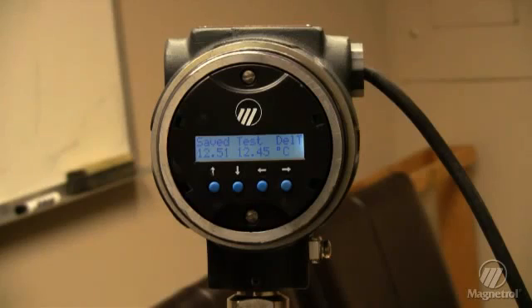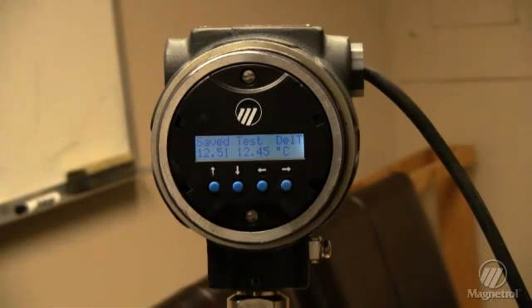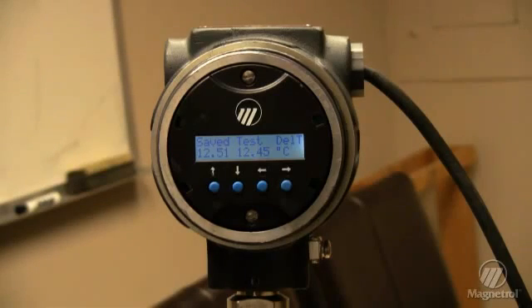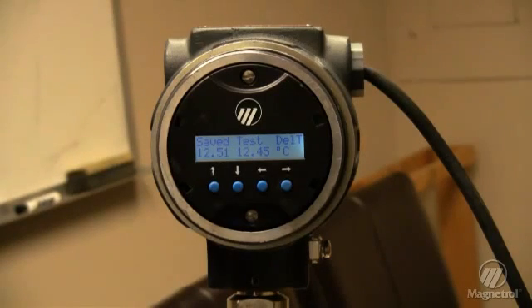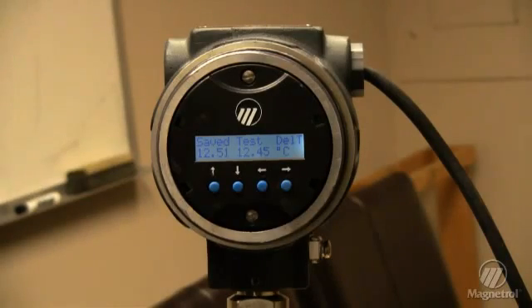If the values are within one and a half degrees, the unit is still within calibration. Some variance in temperature difference is given for variations of ambient temperature as well as test methods. The user can also store the value obtained rather than keeping the original.